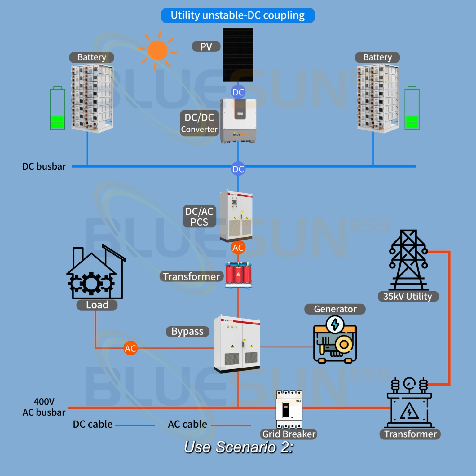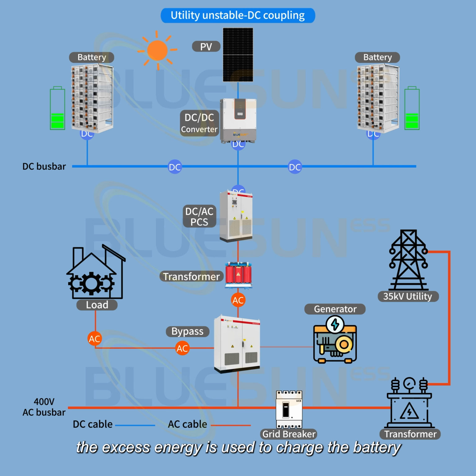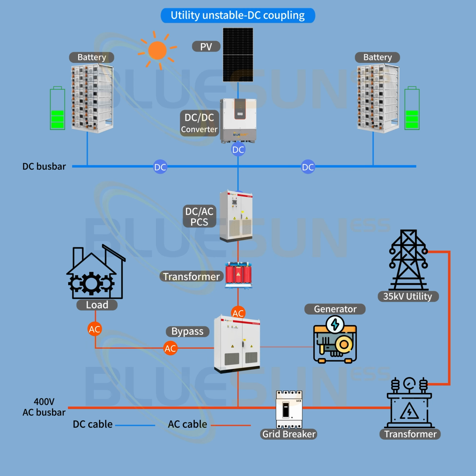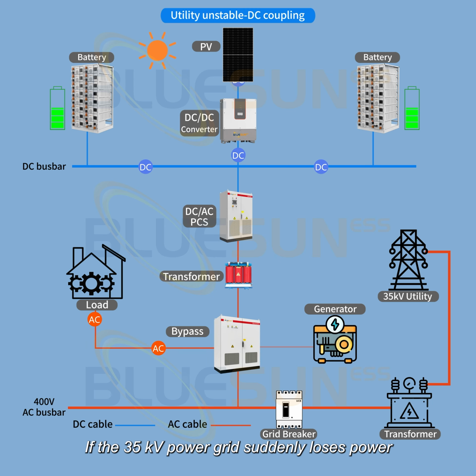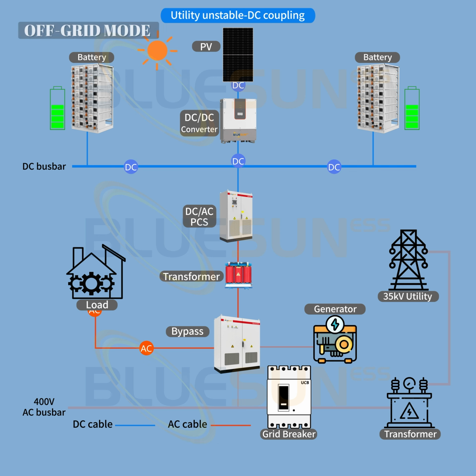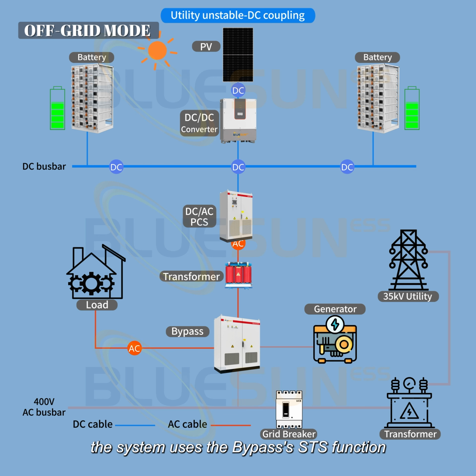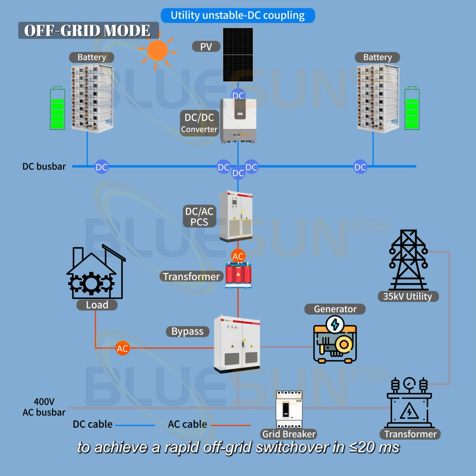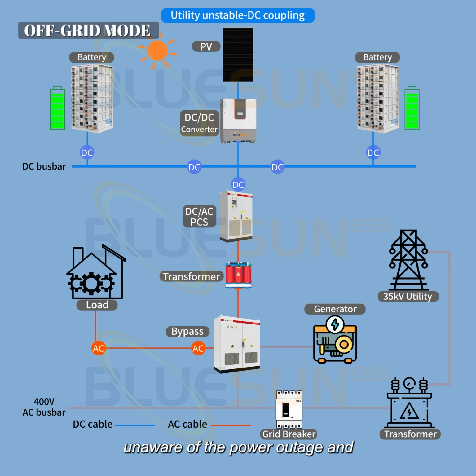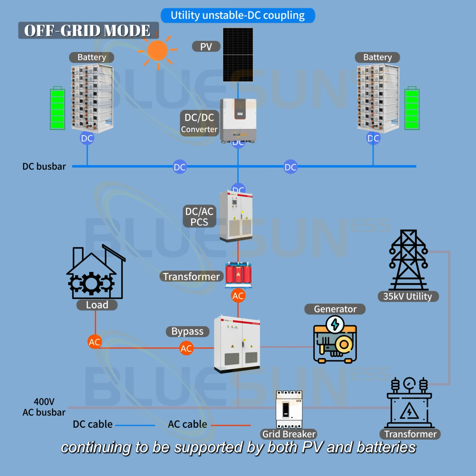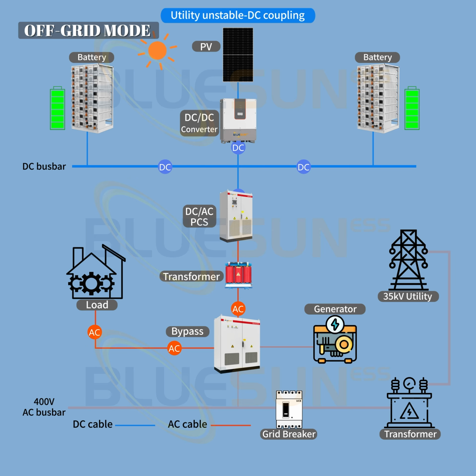Use Scenario 2. Off-grid operation, grid outage. During the day, when PV power generation exceeds load demand, the excess energy is used to charge the battery. If the 35 kV power grid suddenly loses power, the system uses the bypass's STS function to achieve a rapid off-grid switchover in less than or equal to 20 milliseconds, unaware of the power outage and continuing to be supported by both PV and batteries.